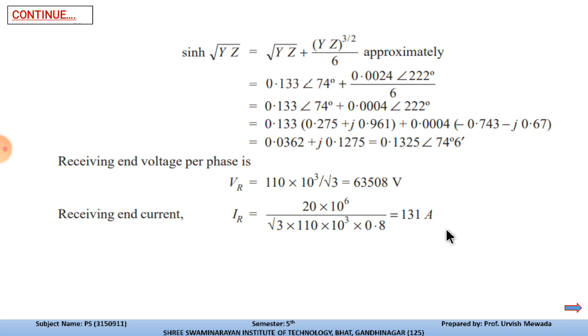Now the receiving end voltage is Vr, equal to 110 into 10 raised to 3 volts, converted from line voltage to phase voltage by dividing by root 3, so 63508 volts. So receiving end current will be Ir, where the power delivered at the receiving end is 20 into 10 raised to 6. This is nothing but the equation P is equal to root 3 V I cos phi, where V is 110 into 10 raised to 3 and cos phi R is 0.8. From that we can determine the value of Ir, that is 131 ampere.